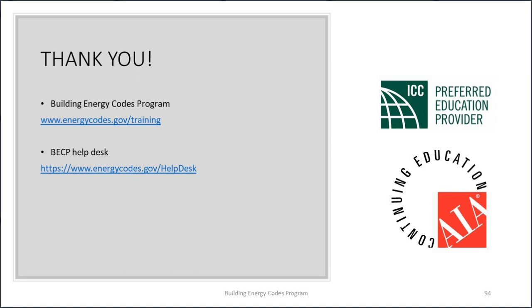Another person asked a question about did the lumen value change? And I think what they're asking is, did the light level change? And yes, that also changed. We did a review of every input we have for the model. We compared it to Illuminating Engineering Society guidance, and in some cases, previous values may have been, let's say, 30 foot-candles, and the model may have only been doing 24 foot-candles, or vice versa, it may have been doing 35 foot-candles. So we recalibrated the model based on guidance from the Illuminating Engineering Society.